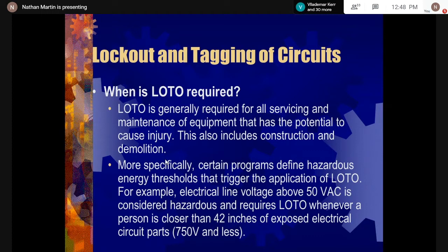Right. However, a lot of the time we don't lock out, but we de-energize, and we carry out work and then we energize. But a good practice is always to lock out the device, right? And they say that whenever the person is closer than 42 inches to exposed electrical circuit parts, so that's basically live parts.